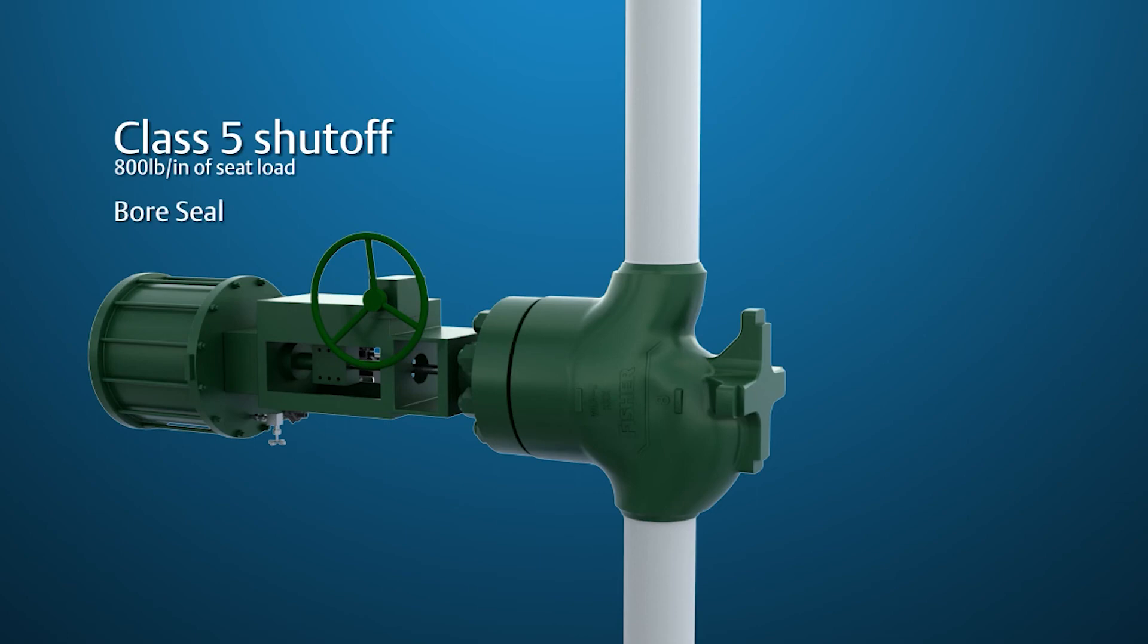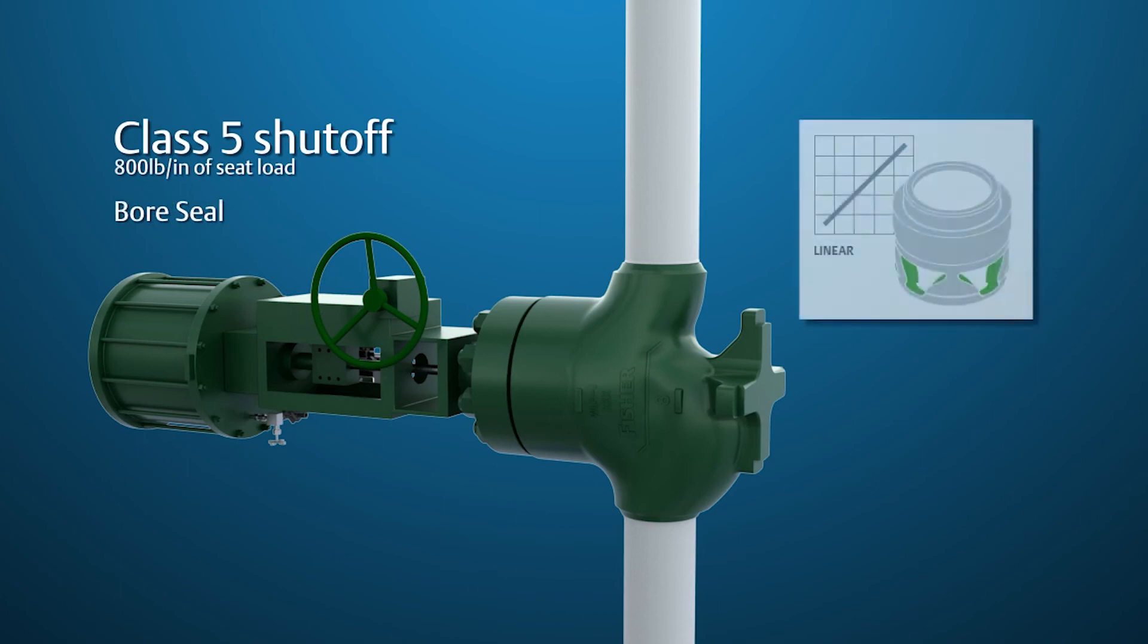Additionally, since the differential pressure is relatively constant, a linear trim characteristic should be used.